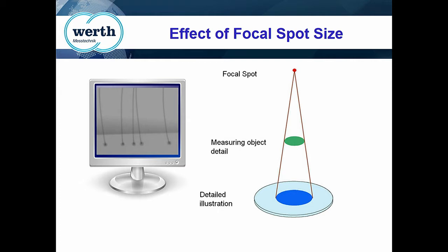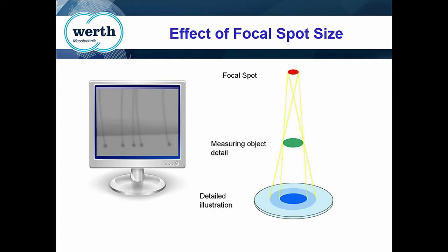This is a nice tight focal spot. Can you go backwards for me, please? And then with a wider focal spot, with your actual live image, you can't compensate. There's no algorithm, because you need to be able to reconstruct this pixel picture into a voxel volume. When you start out with a blurry picture, you can't reconstruct it into a nice tight picture.